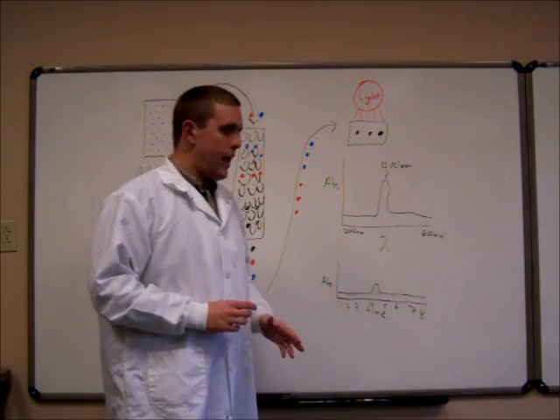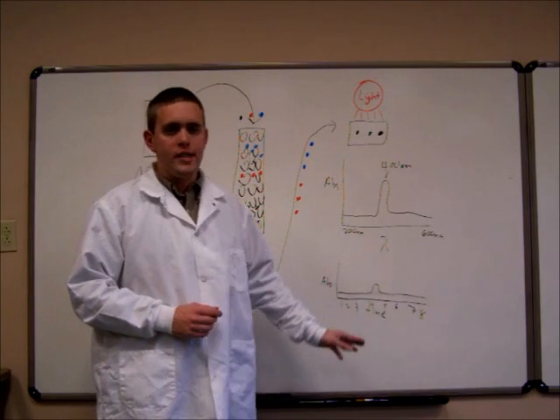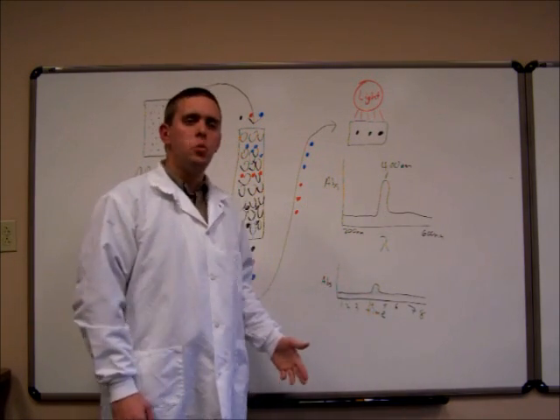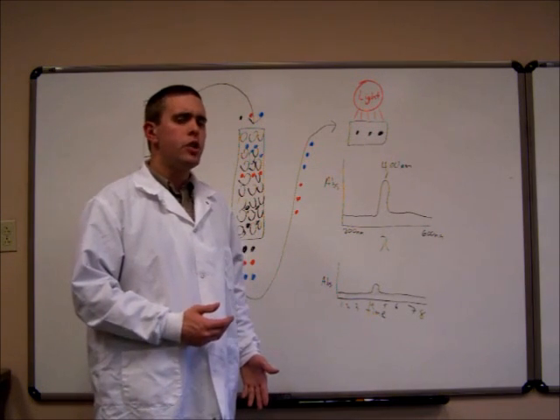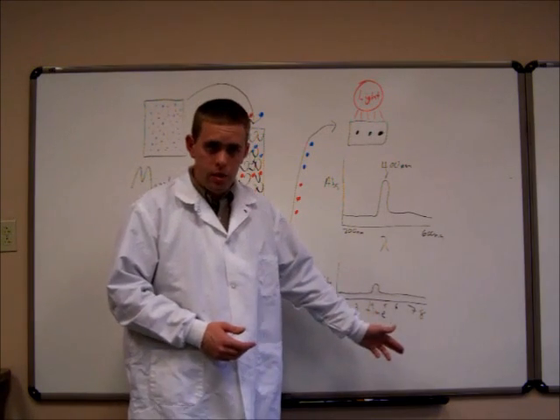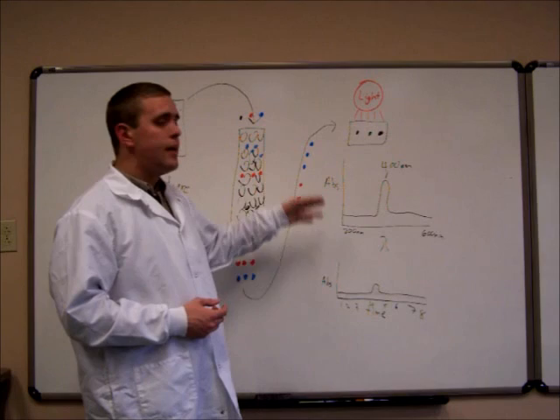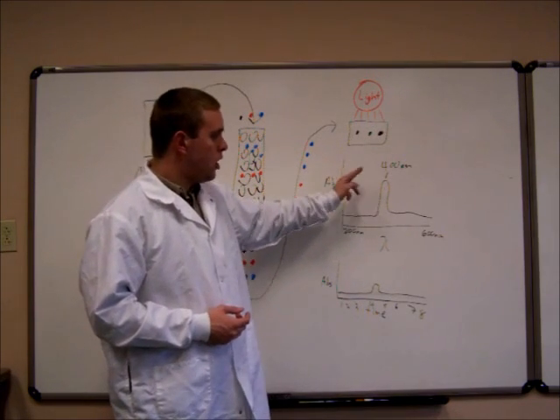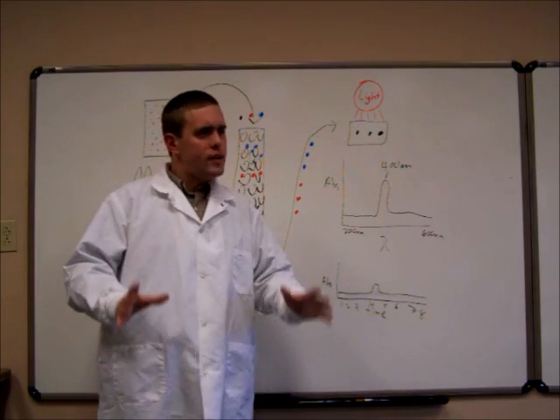The other part of the PDA, the other part of the display you'll be looking at, will show the absorbance over time. The absorbance over time shows when the compounds are eluting out of the tube. So you can determine information about the compounds by the time they elute, depending on your method file, which is something else we'll talk about later, and their particular lambda max. So using this information, we can get an idea. We can determine what is coming out of the tube, what compounds, what analytes we're looking at.